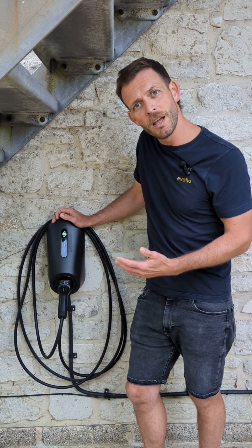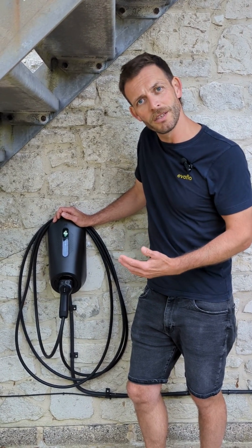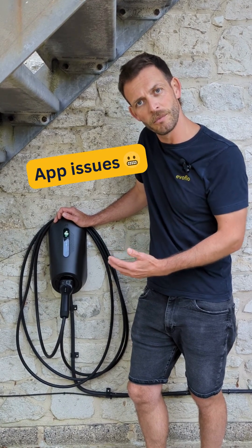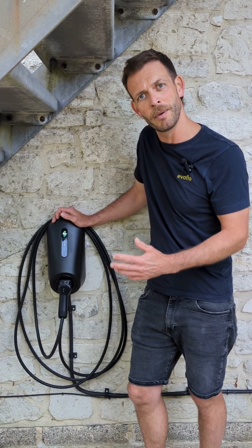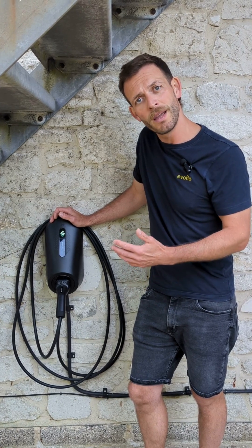What we did find was this customer has solar as well as an AC coupled battery. When there was surplus solar available and the car was plugged in, we couldn't stop the car from charging via the myenergi app — there's no feature and no capability of doing that.